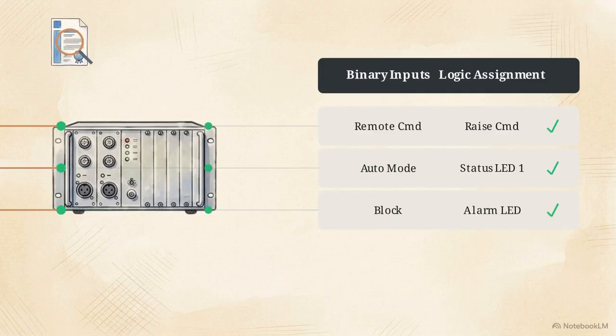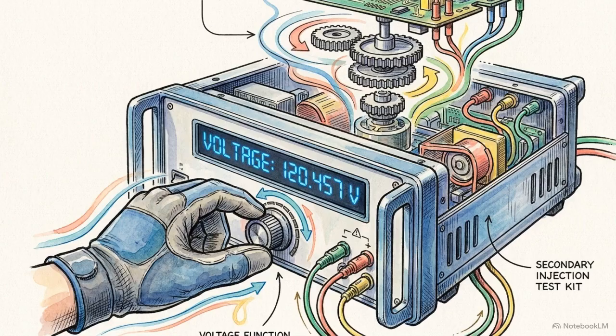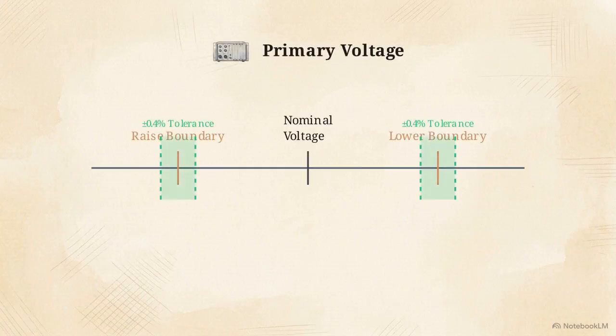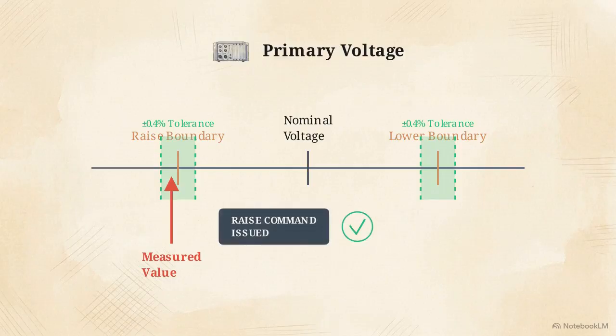schematic. Initiate the bandwidth checks by injecting precise secondary voltage values into the relay. Based on those injected values, calculate the expected primary raise and lower boundaries. Compare those expected calculations against the actual measured values. The component must operate within a strict 0.4% accuracy tolerance.